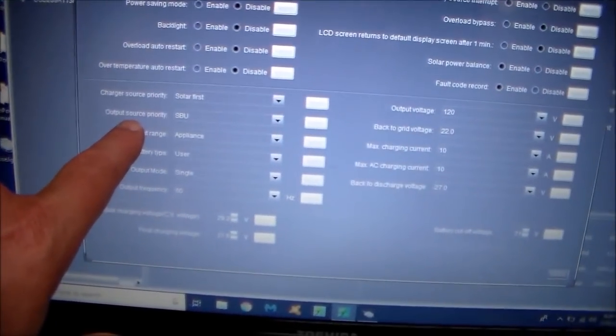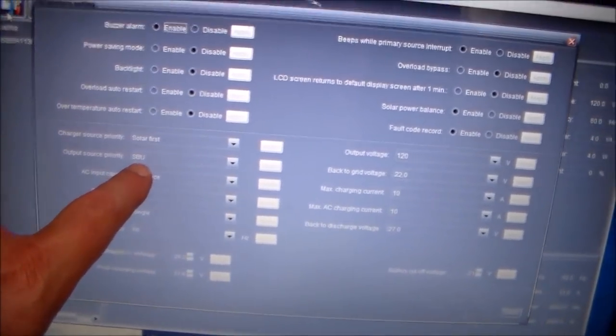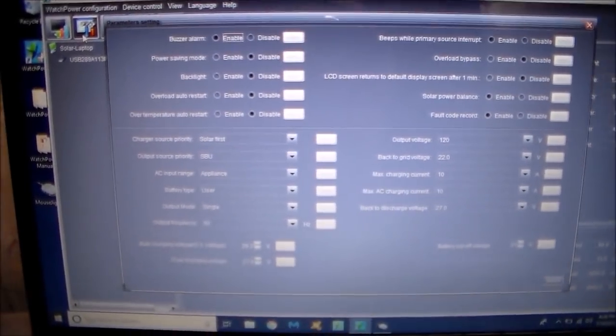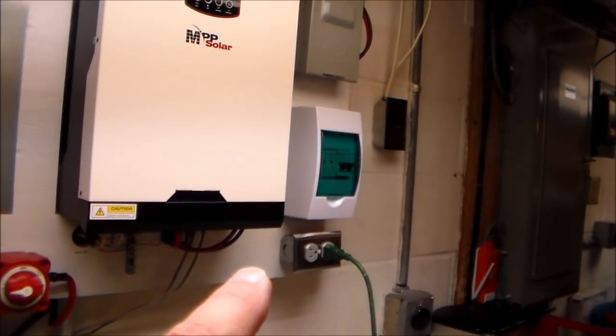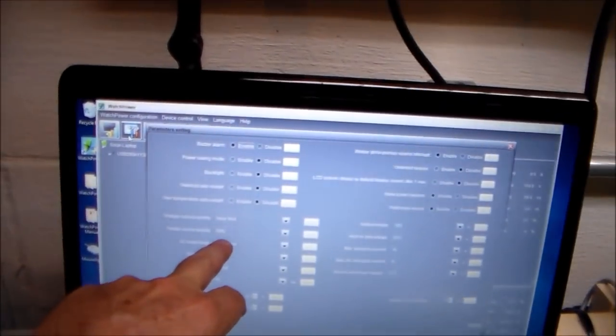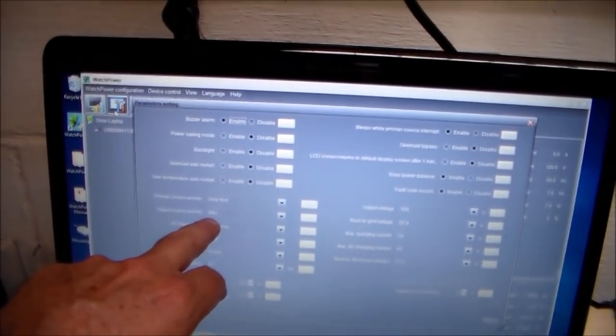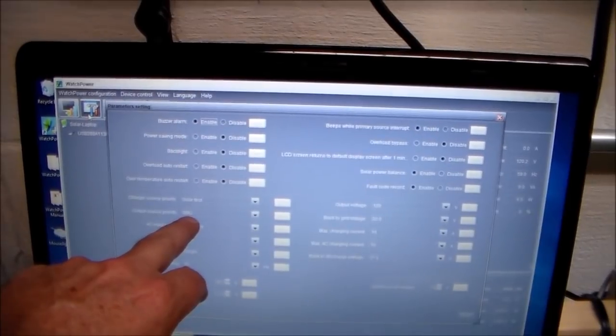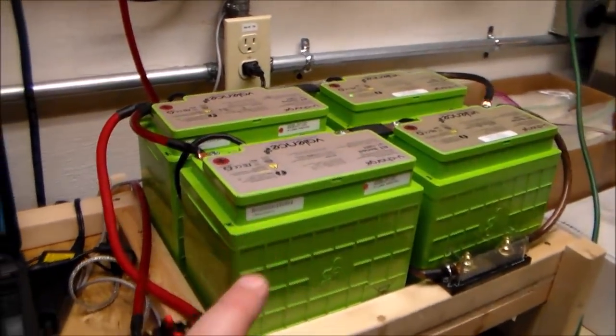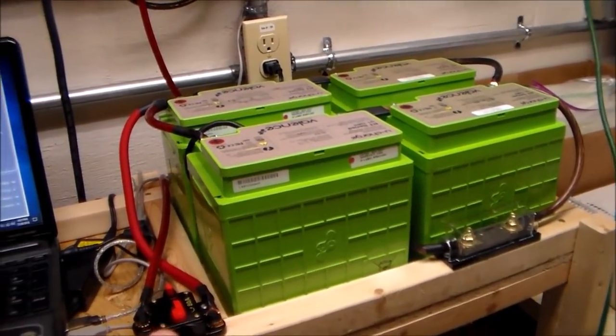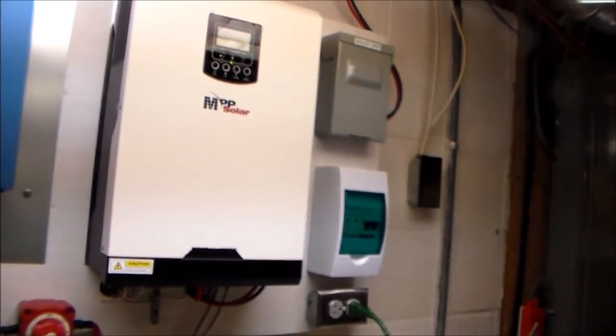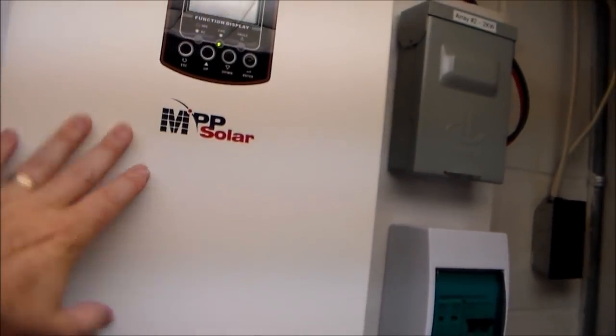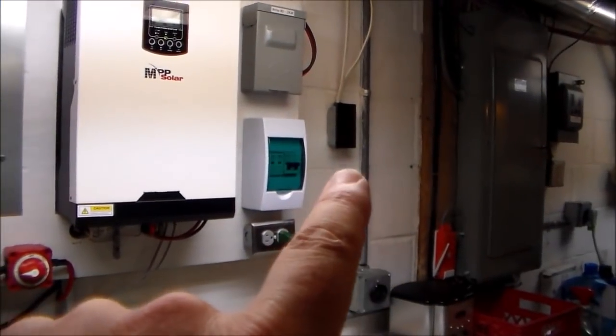The next line I'd like you to look at is the output source priority, and it says SBU. That means my output power, like the dehumidifier I'm running, will use solar power first if enough is available. If not, it'll use the B, battery power, next. And if the batteries drop to a certain voltage, it'll go to U, the utility grid. So this device has an automatic transfer switch, automatically switching back and forth between solar, batteries, or the grid as needed.